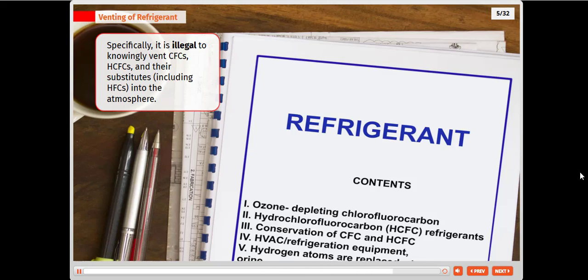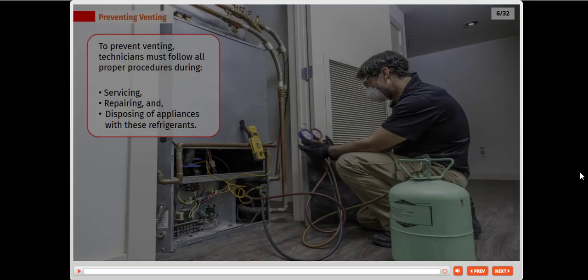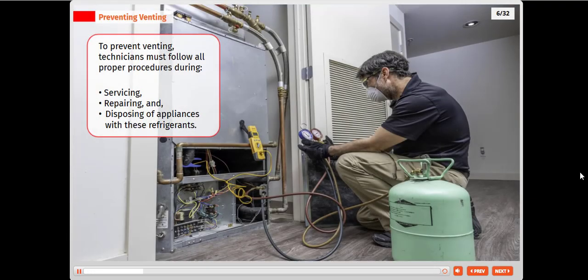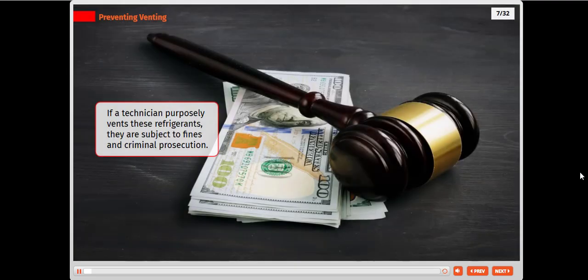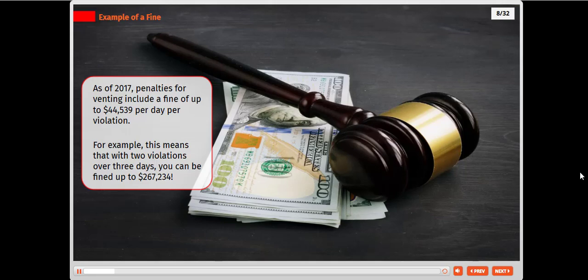To prevent venting, technicians must follow all proper procedures during servicing, repairing, and disposing of appliances with these refrigerants. If a technician purposely vents these refrigerants, they are subject to fines and criminal prosecution. As of 2017, penalties for venting include a fine of up to $44,539 per day per violation.